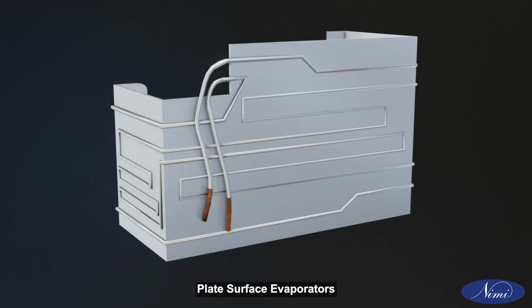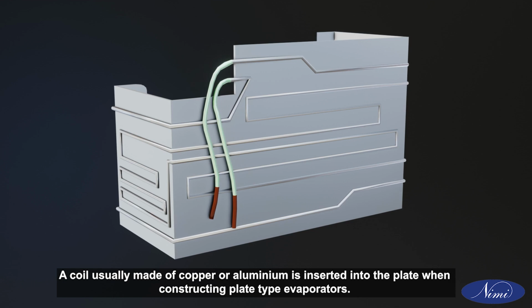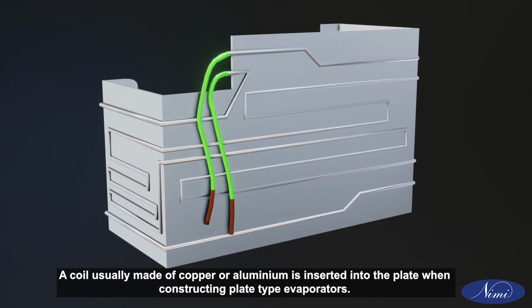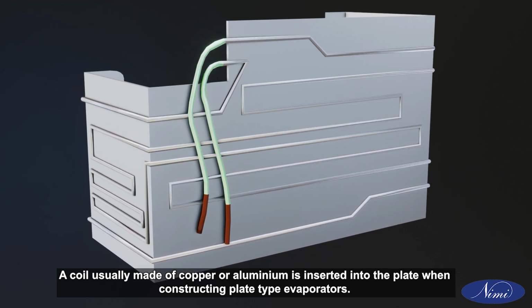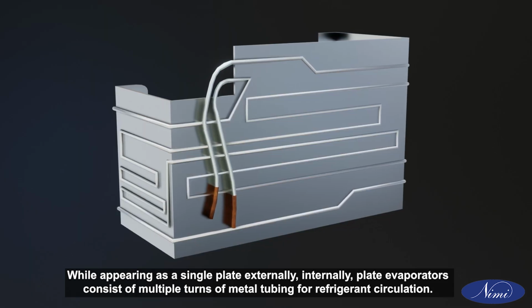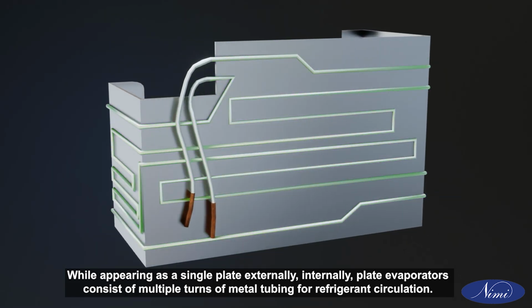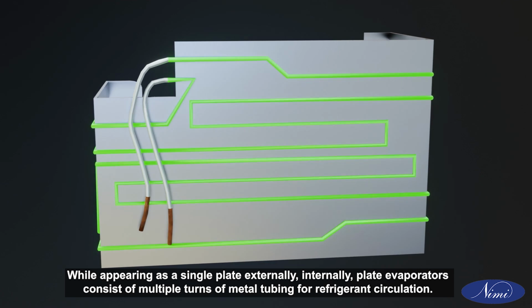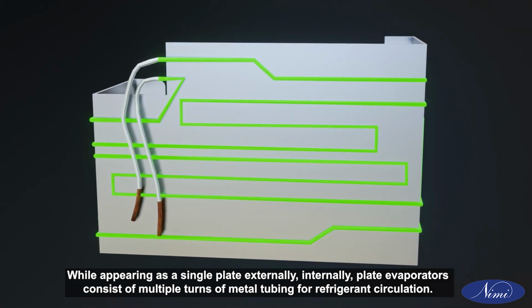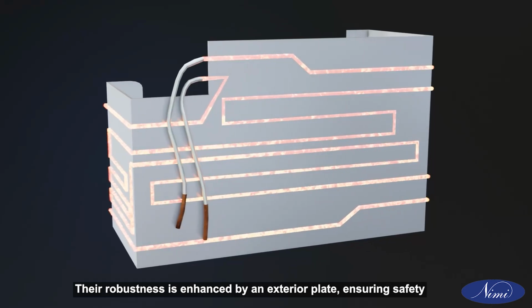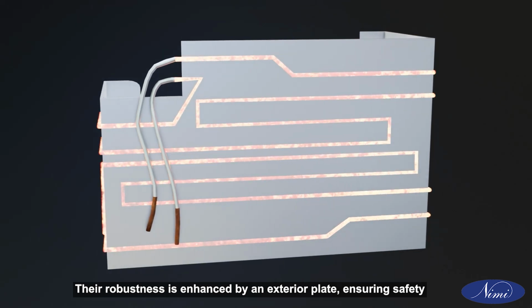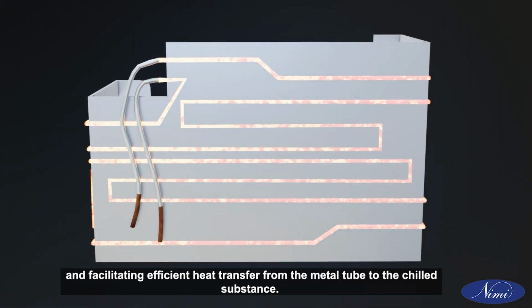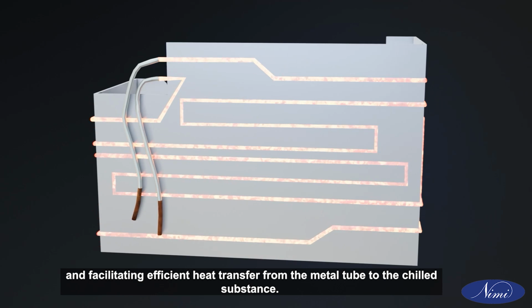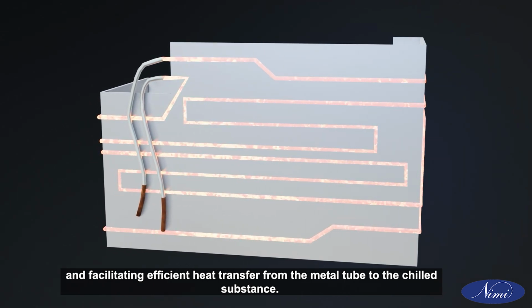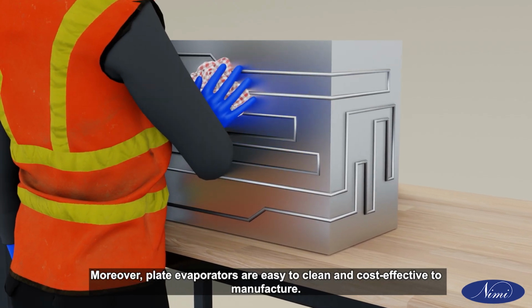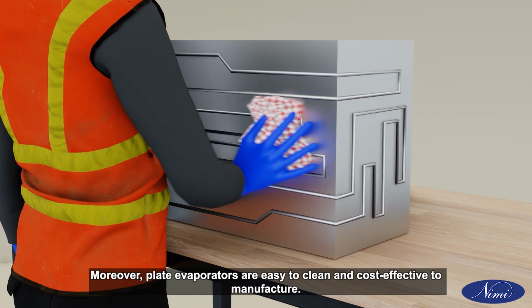Plate surface evaporators. A coil usually made of copper or aluminium is inserted into the plate when constructing plate-type evaporators. While appearing as a single plate externally, internally, plate evaporators consist of multiple turns of metal tubing for refrigerant circulation. Their robustness is enhanced by an exterior plate, ensuring safety and facilitating efficient heat transfer from the metal tube to the chilled substance. Moreover, plate evaporators are easy to clean and cost-effective to manufacture.